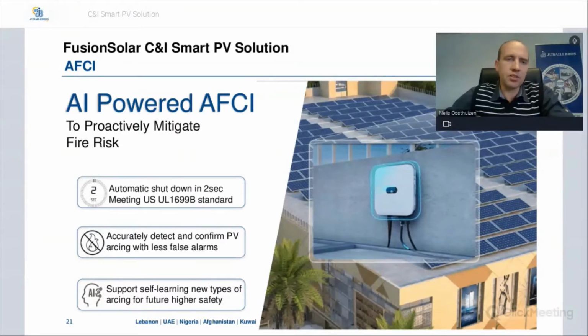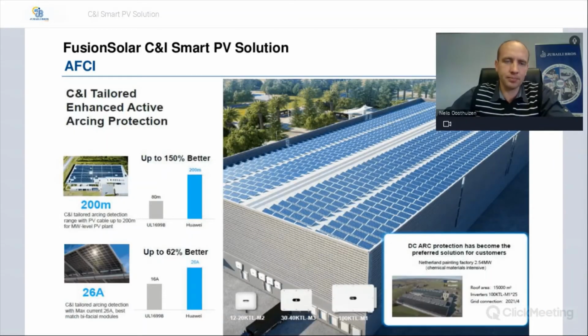As I mentioned, it has artificial intelligence powered AFCI. It has automatic shutdown in 2 seconds, meeting the UL 1699B standard. It can accurately detect and confirm PV arcing with fewer false alarms, and it supports self-learning of new types of arcing for higher safety in future.